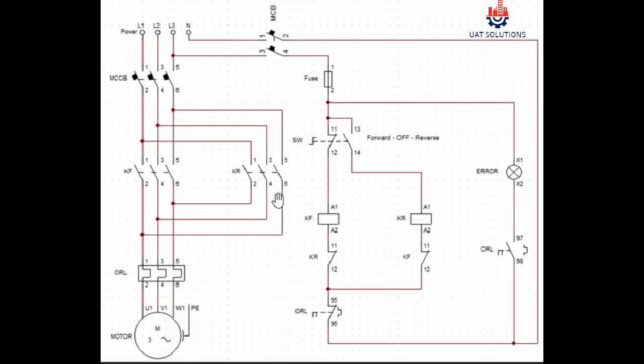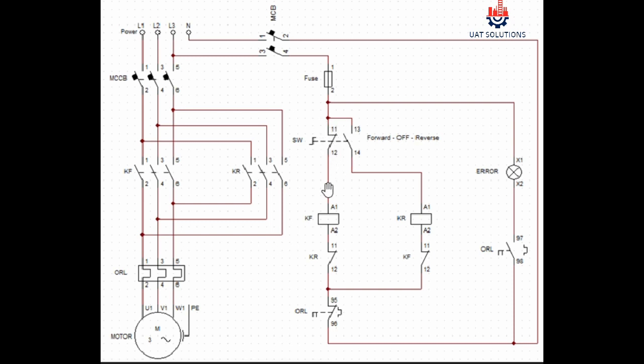Now we understand the wiring, we can visualize the operation of the starter. Once the selector switch is turned to the forward side, point 11 and 12 will close and phase is supplied at coil terminal A1 of contactor KF.